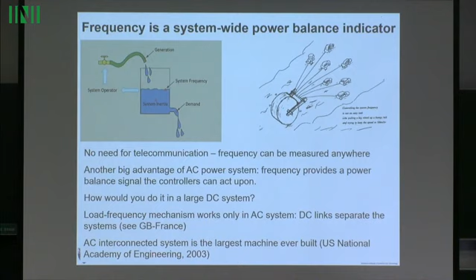A few slides relevant to the research we've been discussing concern the concept of inertia: the bigger the system, the more stable it is from a frequency control point of view. So in continental Europe, because it's huge, any disturbance causes very little variation in frequency - it stays very close to 50 hertz. In this country, the National Grid has a statutory obligation to keep frequency deviations within 0.1 hertz under normal circumstances. It can drop below that, but only for some big event - normally they keep it within plus or minus 0.1 hertz. This is an example from Ireland, which is a bit like Britain.